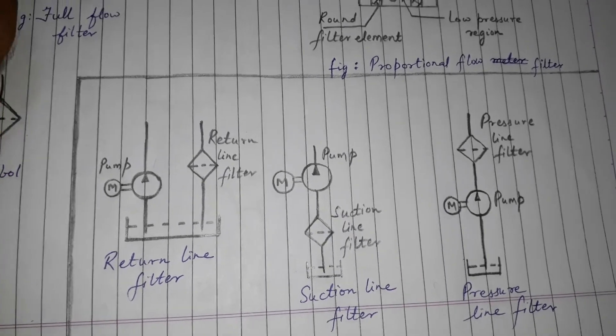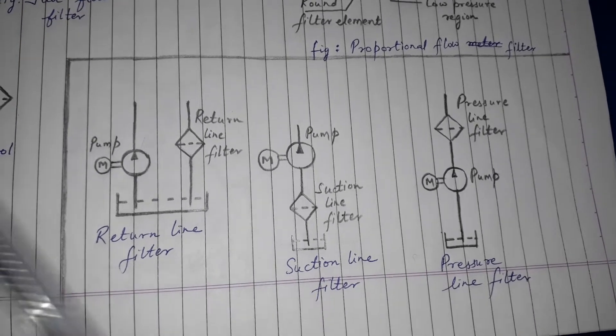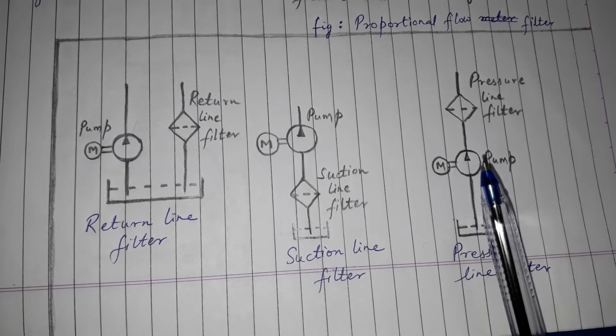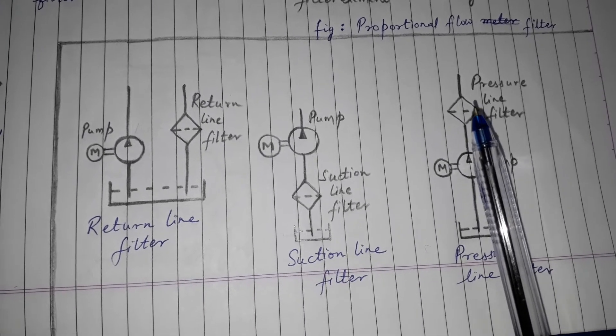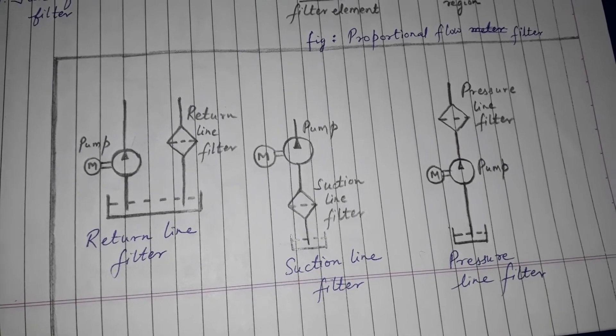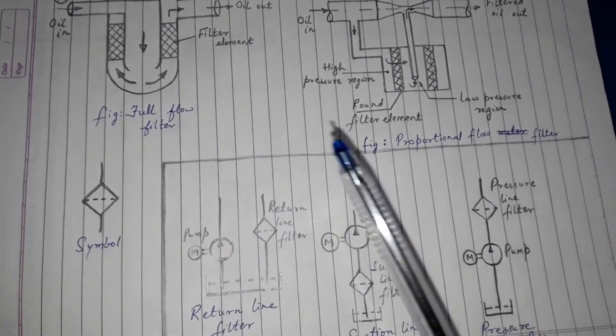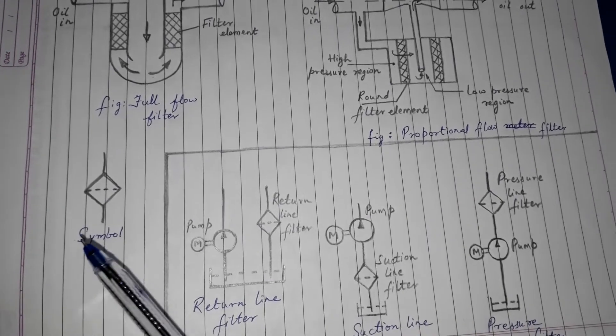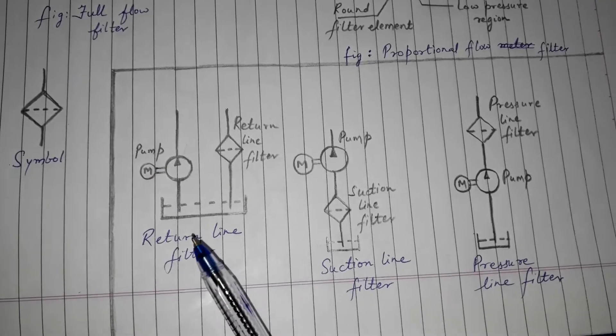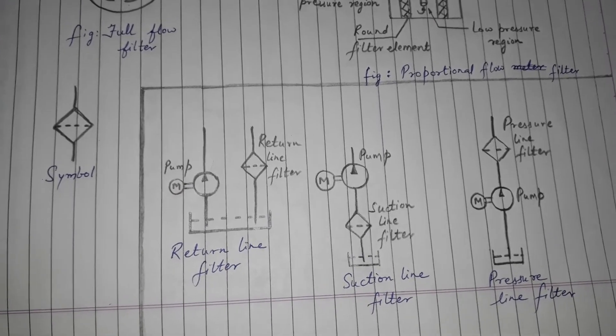The second location is the suction line filter, where the filter is on the suction line of the pump, so the oil is filtered before entering the pump. The third is the pressure line filter, where the filter is located after the pump, on the delivery side. So we have covered full flow filter, proportional flow filter, the symbol of the filter, and filters based on location.